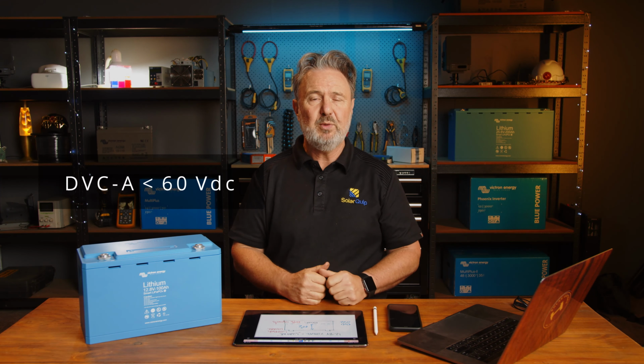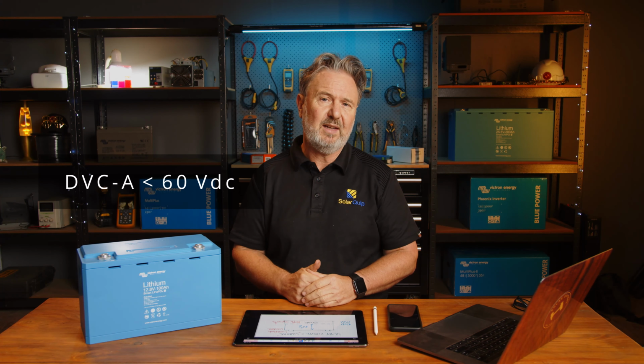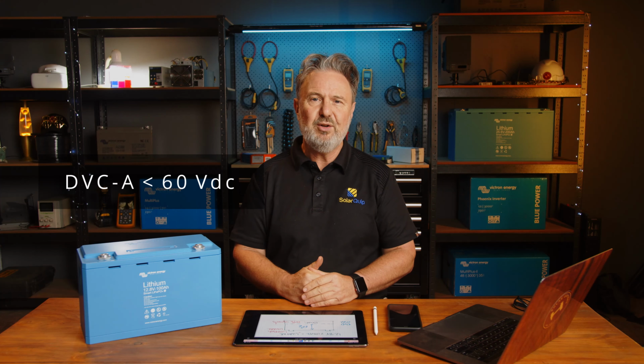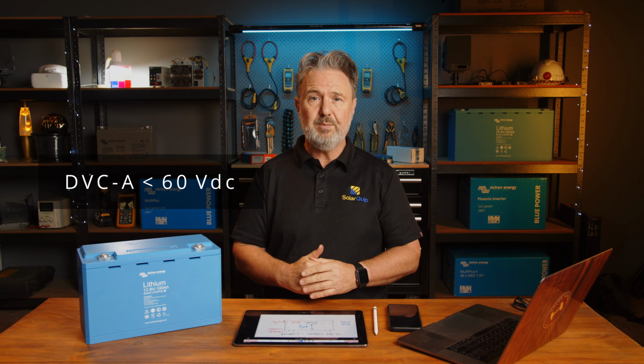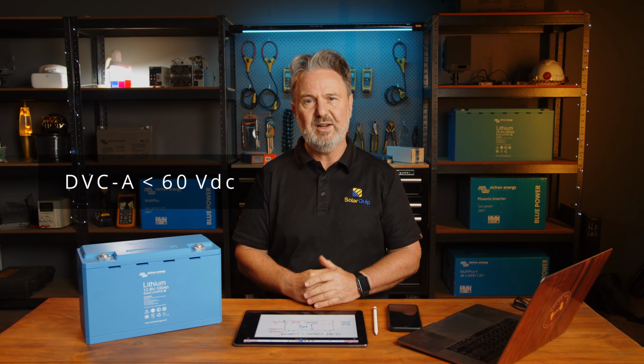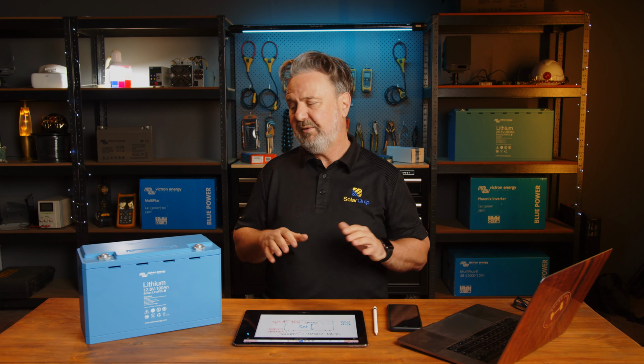The three categories are: DVC-A, which is up to 60 volts—specifically, no greater than 60 volts for more than 0.2 of a second under any operating condition. That covers just about all nominal 48 volt lead acid batteries except flooded ones, since flooded lead acid will often go over 60 volts under an equalization charge. Otherwise, for most lead acid and lithium, nominal 48 and 52 volt lithiums are all under that 60 volt mark.